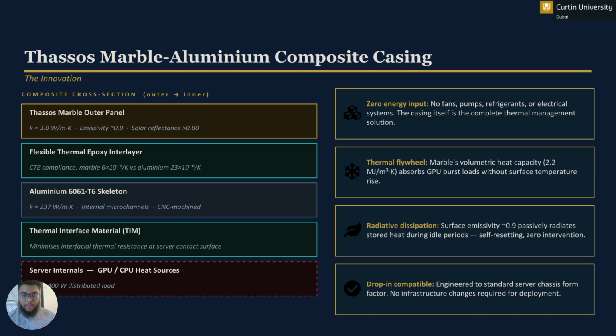The aluminum skeleton, with a thermal conductivity of 237 watts per meter Kelvin, provides rapid in-plane heat spreading. The marble layer provides thermal mass, surface emissivity, and reflectance that enable passive dissipation. And along with that, we also have ventilated cutouts in the marble panels to allow natural convective airflow. Internal microchannels within the aluminum skeleton also provide the option for hybrid cooling integration in higher load configurations. And the result is a casing that is structurally equivalent to a standard aluminum chassis and is thermally superior for the specific workload pattern of AI inference deployment.